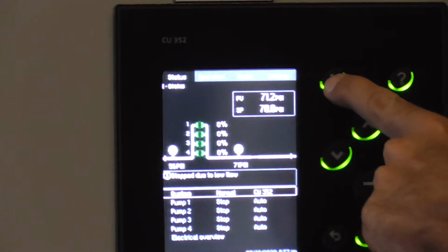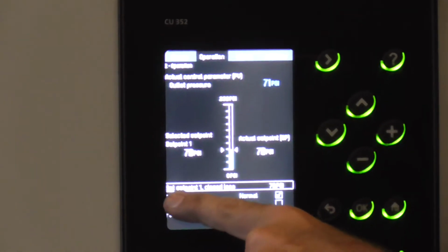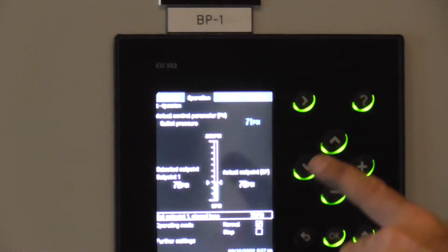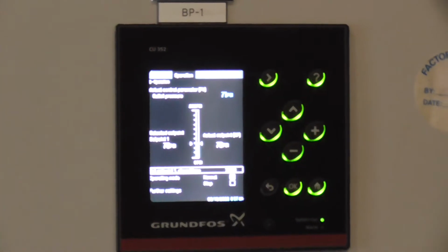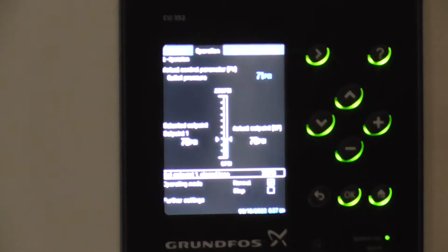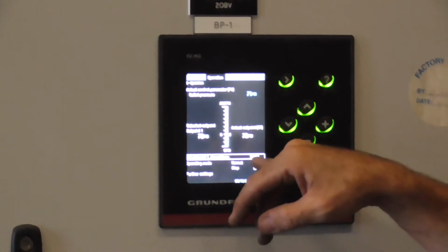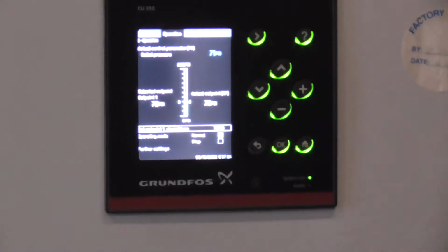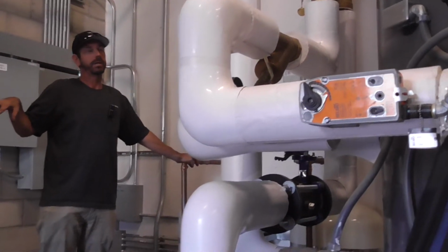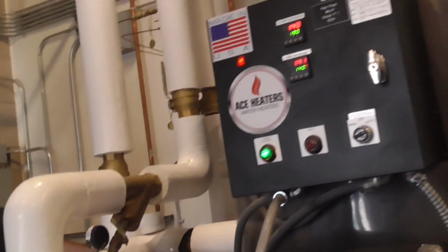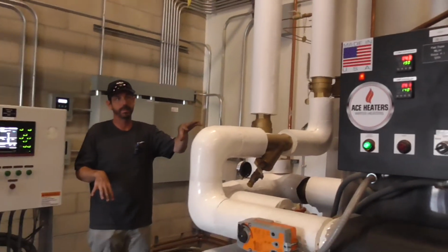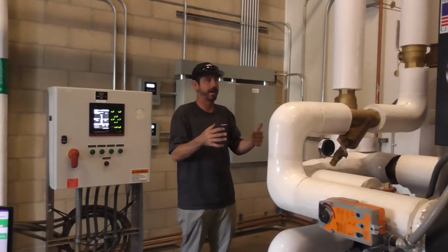To make an adjustment here, we're going to use the arrow button and go over to operation. This is where our set point is, we're set at 70 psi. That gives us about 30 pounds up on the roof for the engineer. You can make an adjustment here, just make sure this booster pump skid has an expansion tank on it, which is over here. This expansion tank on the left goes with the booster pump skid. There's another one on the right, which is the expansion tank for your closed loop heating, domestic hot water system, for thermal expansion for the heating on the domestic hot side.